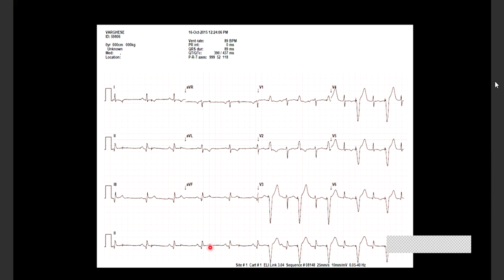The reason for loss of capture, one, may be inadequate output. That is not the case here. Second, may be a lead problem. Or third, the output may be occurring during the physiological refractory period, and that's why there's no capture. Here you can see it's falling on the QRS complex and the T waves. Whenever an output falls there, you're not expecting capture because that is the refractory period of the ventricle. But when it falls outside the QRS complex, you're expecting capture. So here, the loss of capture is more likely because it's falling on the refractory period.